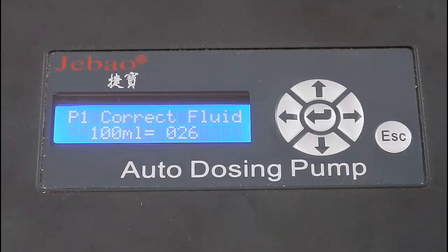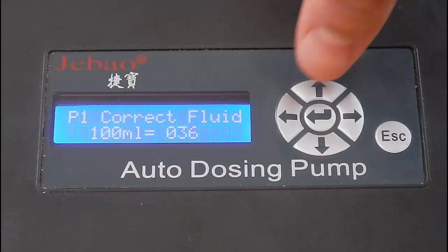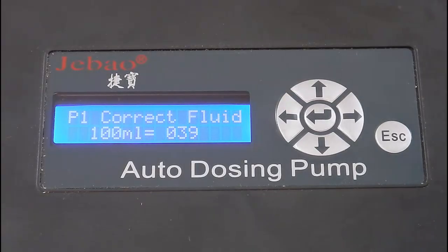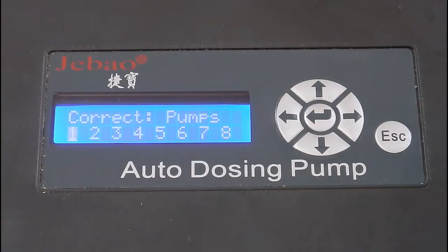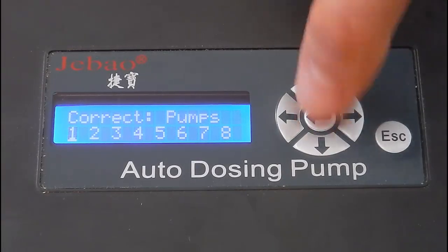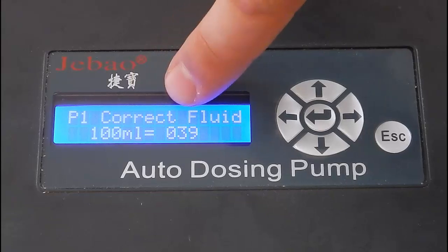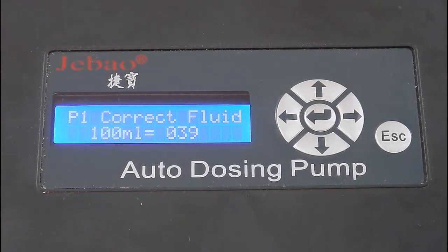Now you're going to see it filling up. Once it gets to 100 milliliters, say it's at 100 right now, go ahead and hit the top button to stop the process, then hit the middle button, and that calibrates that pump. So you can go back into that pump and you'll see 100 milliliters equals 0.39. Now 0.39 is obviously not what it takes to calibrate that pump, so let's go ahead and get into calibrating.